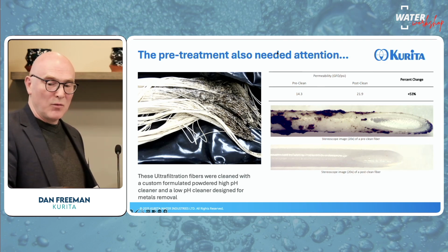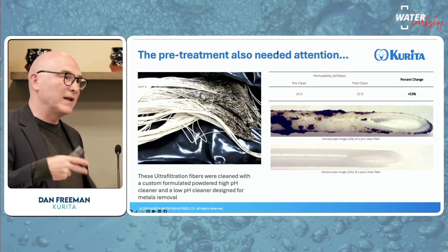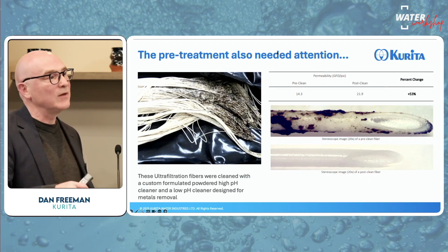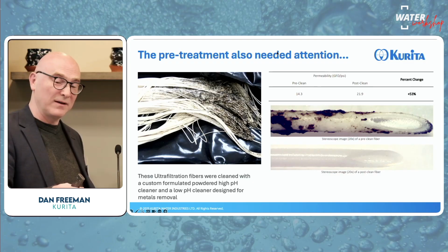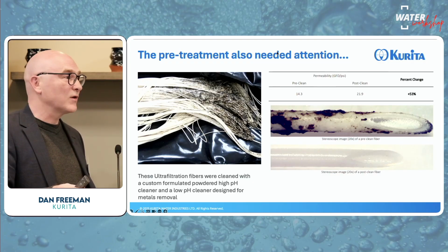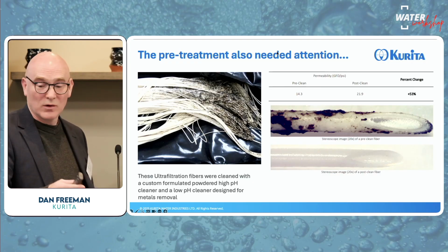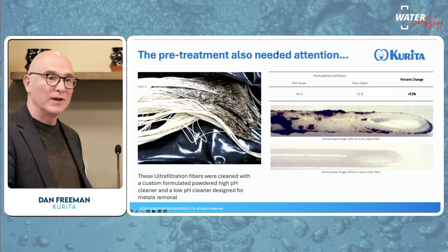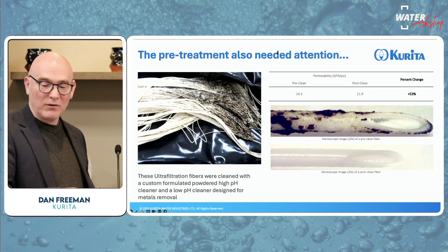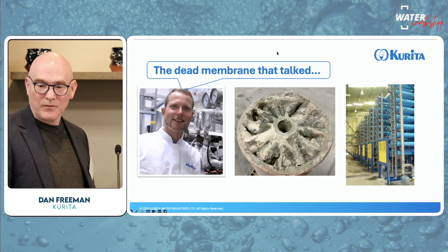If you can use a more formulated cleaner, which is more effective, you can get a better clean with that than you would generally expect to get with sodium hydroxide, for example, or an acid. In this case, we used a formulated cleaner, and we can see a big improvement in the performance of the module.